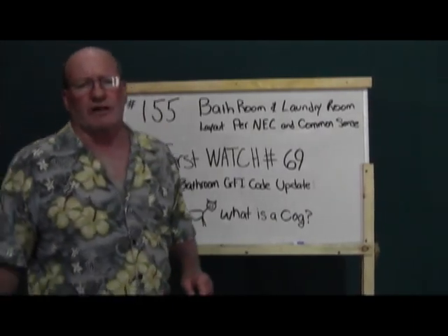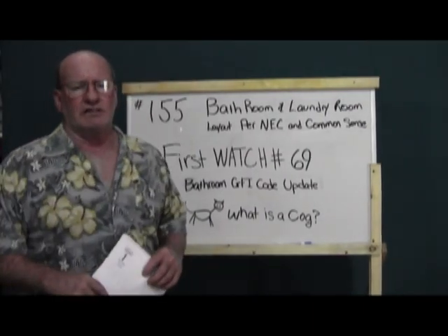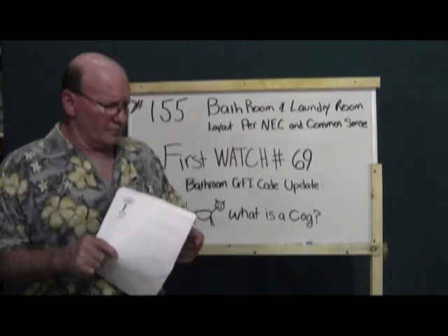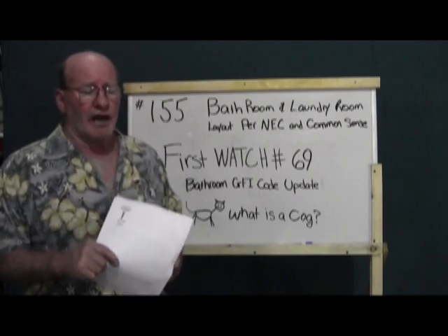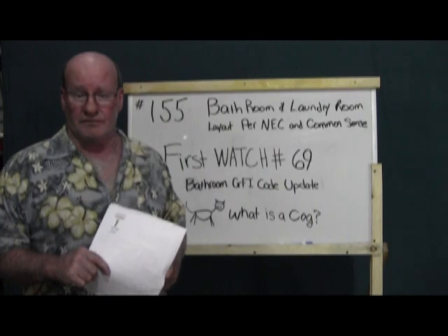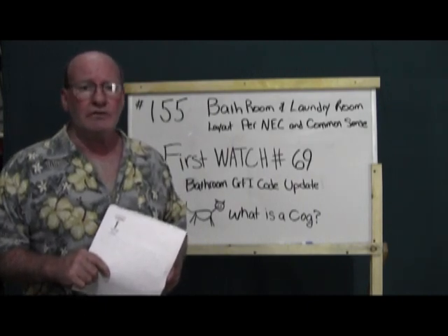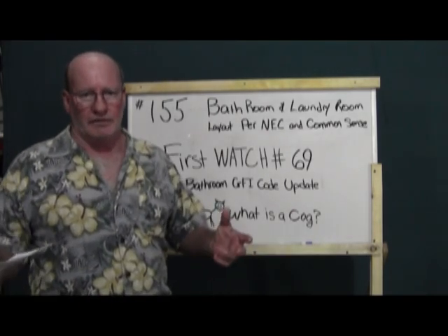Maybe I'll tell you what that is in my next episode. It totally slipped my mind, and I do apologize that when you're building a house and laying it out, you have to have an outlet in the hallway if it exceeds 10 feet, and you have to have an outlet in the stairwell no matter what. Hallways, you get an outlet, and stairwell.